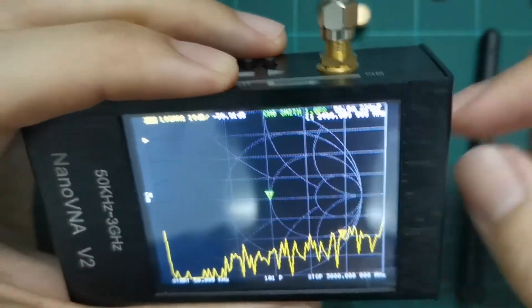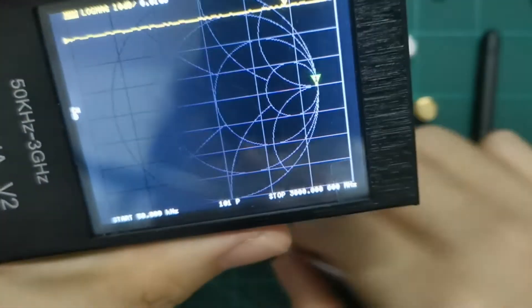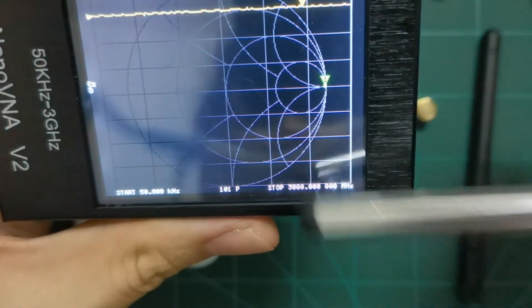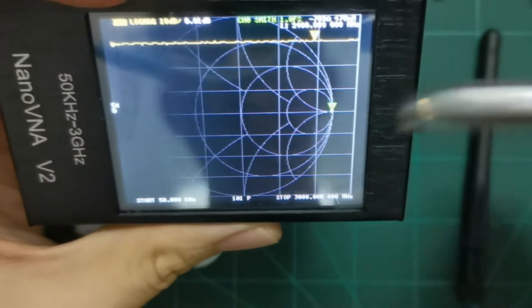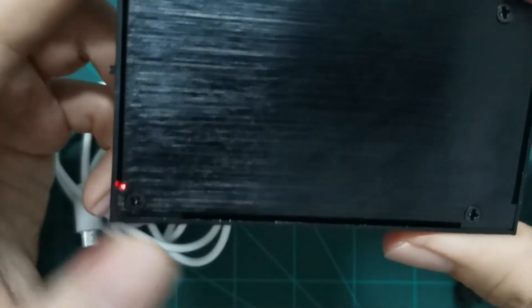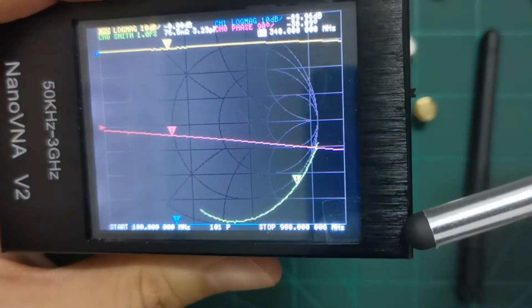Let me show the saved state recall. Remember our calibration was set with start at 50 kilohertz and stop at 3 gigahertz. I'll turn the device off — you can see the built-in battery indicator. When we turn it back on, it resets everything to the default 900 megahertz range.